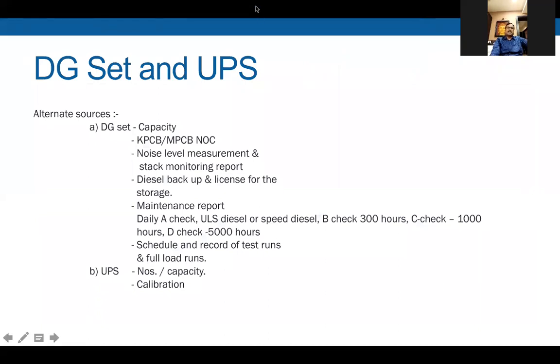So now I come to DG sets and UPS, again an important installation in the hospitals. This is an alternative supply of power, all of you are aware, and this is required at least for critical areas. DG sets in smaller hospitals, people don't want to put a higher capacity, which is all right, but at the same time, the DG sets must cover all the critical areas where the active patient treatment is going on. Maybe you can cut corners with the outpatient departments or various other back-end departments, but not with the ICU, with the operation theater, with various critical areas where you are doing an intervention like cath lab, etc. So this has to be of that much capacity.